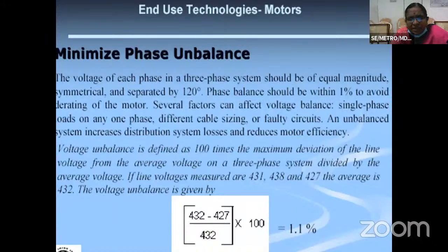This is also there. Minimize phase unbalance. Whenever we are using a three-phase system, there should always be a balance of loads in all the three phases. We have typically measured, we have concluded even in distribution transformers also, we have calculated the losses when there is an unbalance of load, and after balancing all the three phases, we have calculated the losses, it is very less. So there should always be a balance in all the three phases, which could reduce the losses.